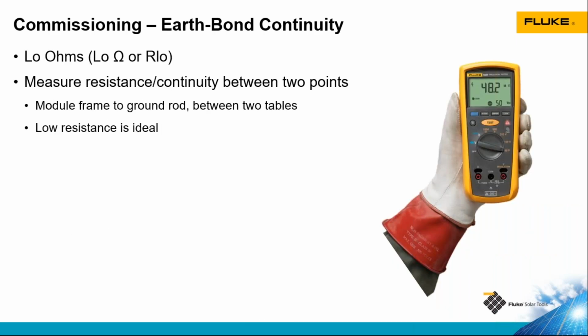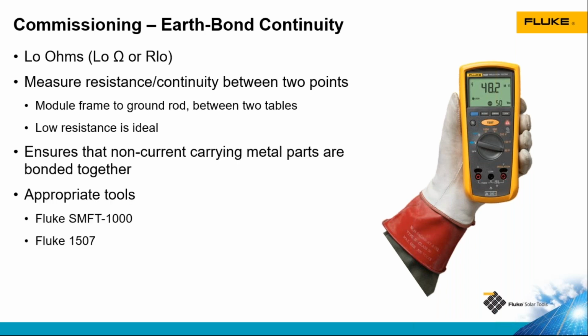Another test we do at commissioning is earth bond continuity. This is ensuring that all of our non-current carrying metal parts are electrically connected together. So making sure that our module frames are bonded to the racking, which is bonded to the conduit, to any type of metal disconnect, combiner box, inverter enclosure. We want low resistance there to make sure that if there is a ground fault, that current has an easy path to ground, not through our technician, to increase safety. And also some overcurrent protection devices like circuit breakers need a path to ground in order to function properly.